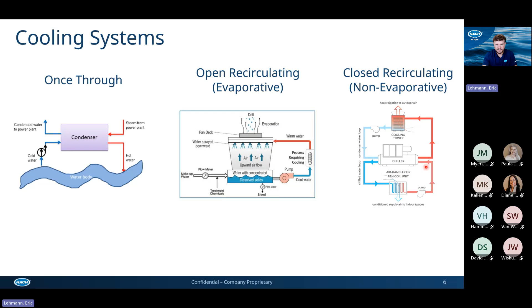We also have an open recirculating system, or evaporative system, which we'll get into, and the closed recirculating system, or non-evaporative system. Systems like this often use glycol-based coolants, so it's completely closed loop. You don't have the evaporation that you might have on an open recirculating cooling tower, which is why it's more of a non-evaporative closed loop system.